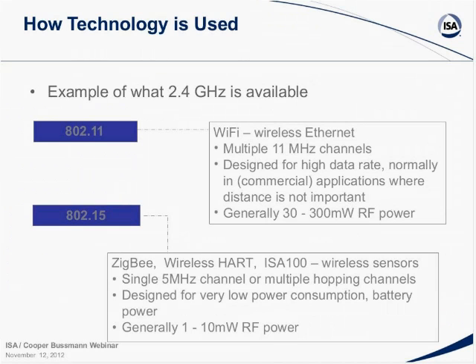The more common one used for field sensor networks uses an 802.15 radio. Again, it's made to be compatible with 802.11, so there are some things built into it so that these two don't fight. You'll notice that 802.15 is a 5 megahertz channel, so it's a smaller channel. If you pick the right channels in 802.15, you can almost avoid the ones most commonly used in 802.11 and thus get better reliability.